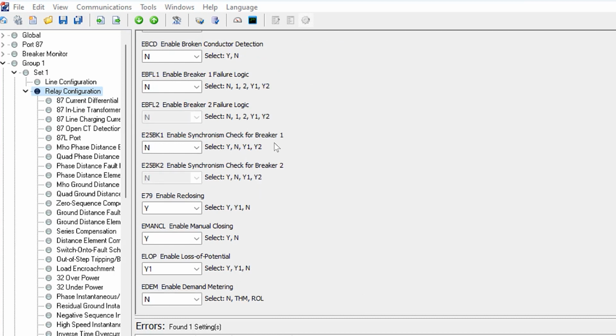For this example, I'm just going to focus on one breaker. So we're going to say that we're going to implement the sync check element on the bus 1 breaker. So I'm just going to enable one breaker. But again, just know that if you were to implement this for both breakers, you would of course need to set both sync check elements. So I can set this to yes, but notice over here that we also have Y1 and Y2 options.